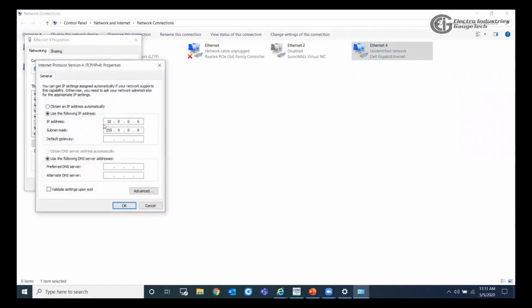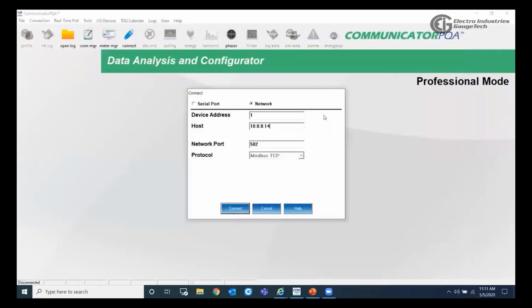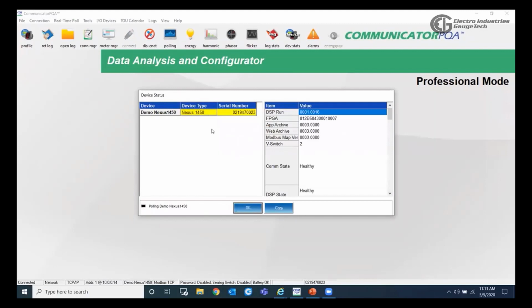And I would set my laptop IP address to be on the same IP address range, like I'm setting here 10.0.0.6. And no need for the default gateway when we are connected directly with the meter. So going back to the communicator, using the connect icon here, I would get the same device status window once I connect to the meter. So that's all about how we can connect for the Nexus 1450.